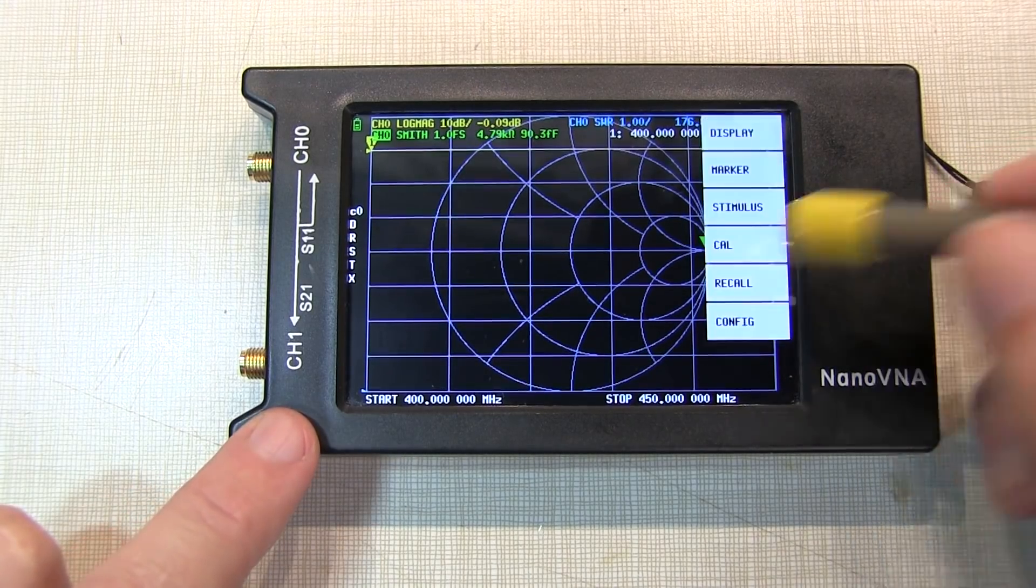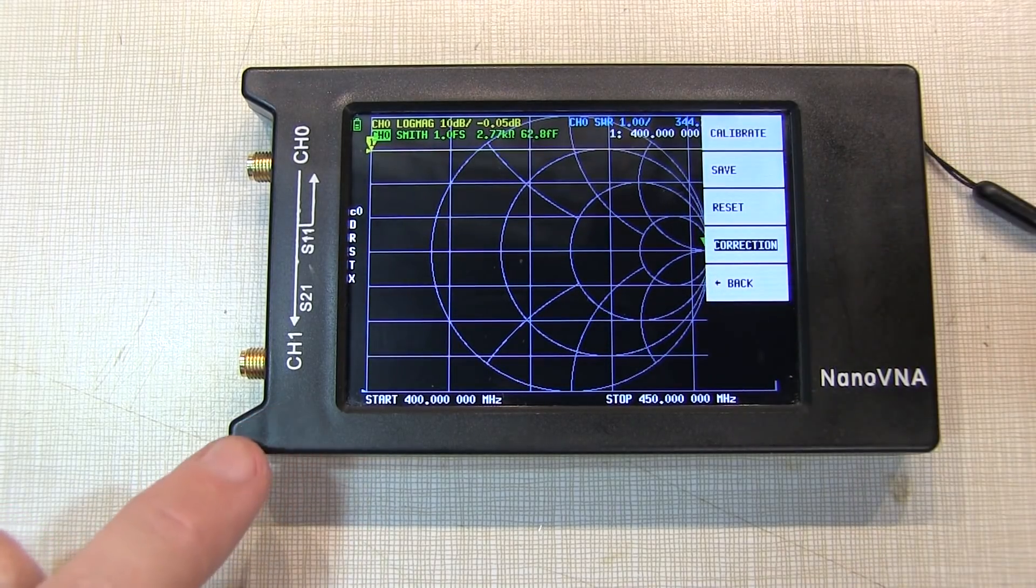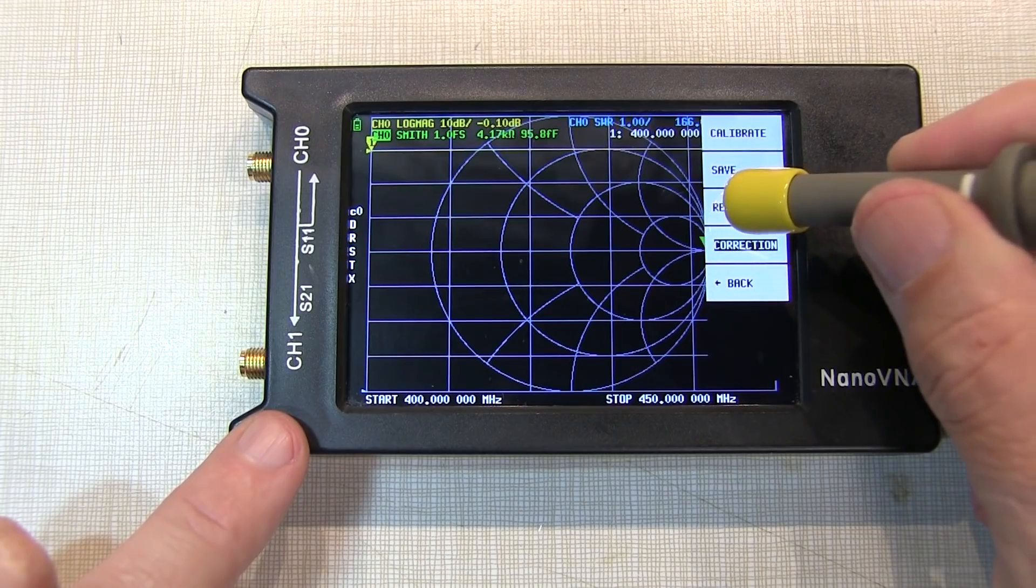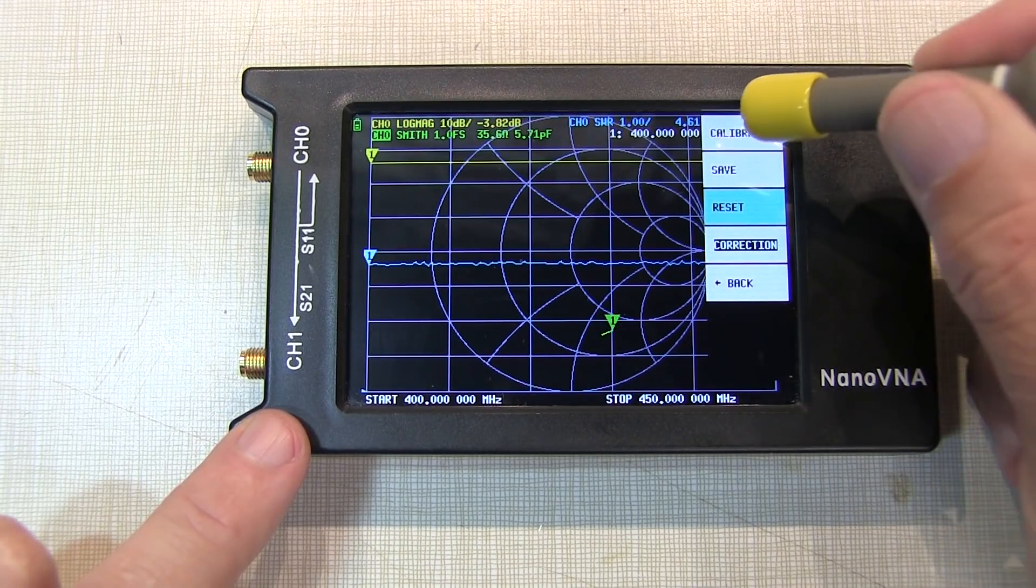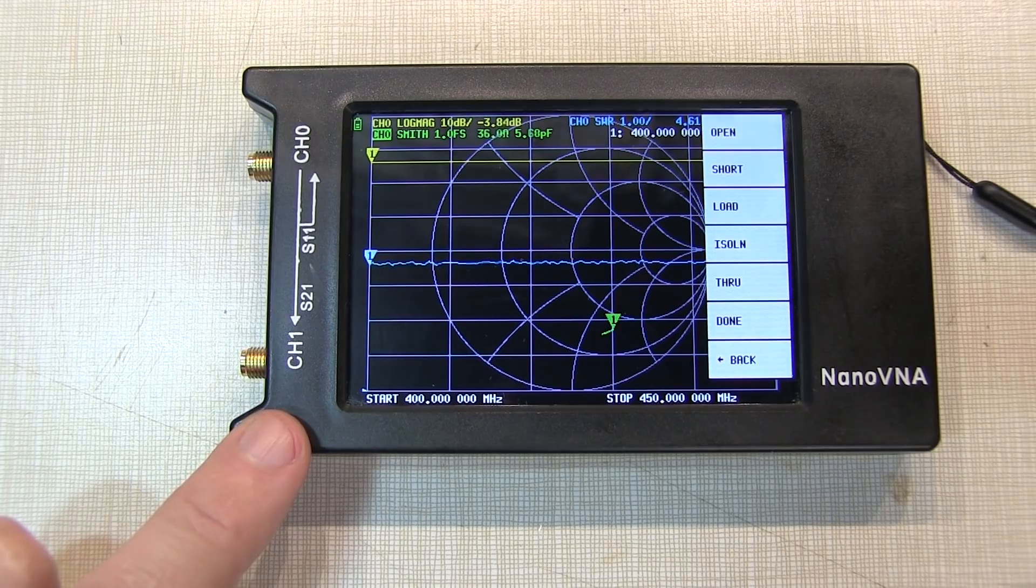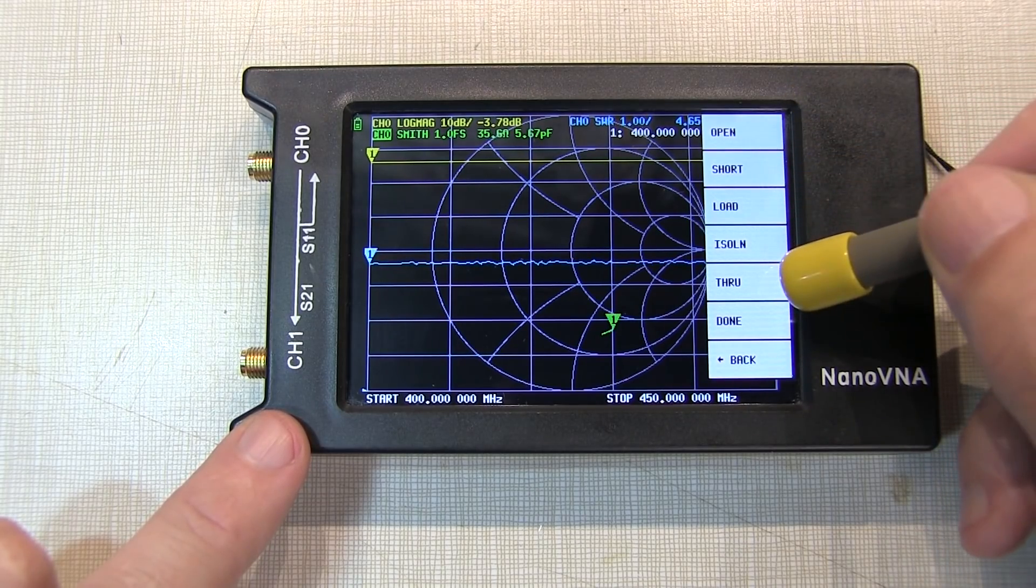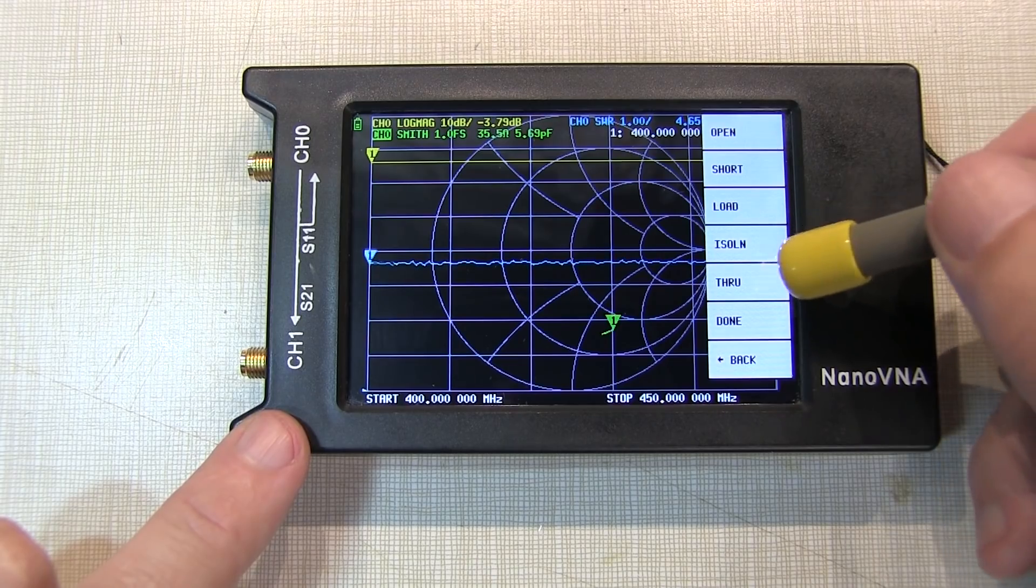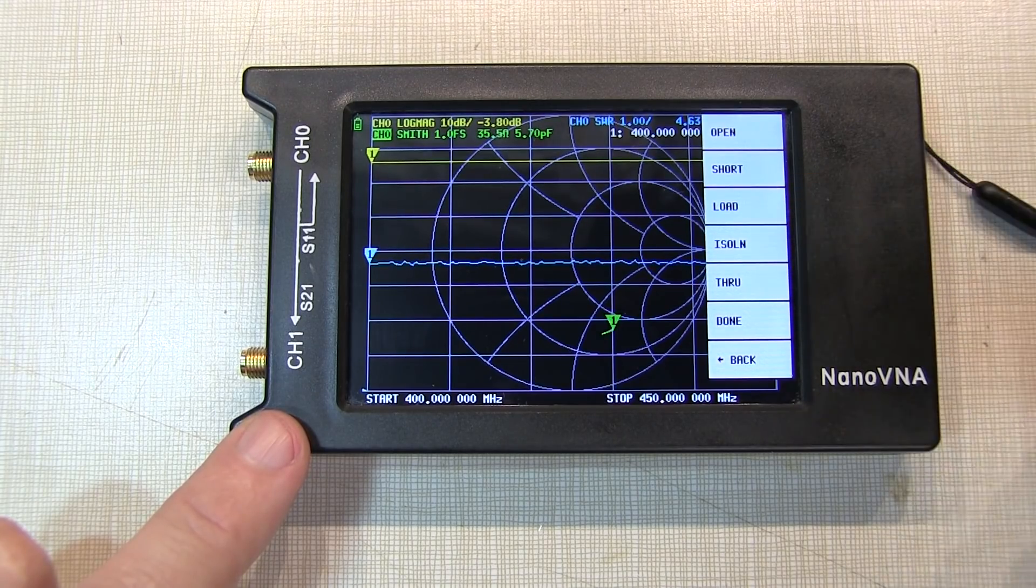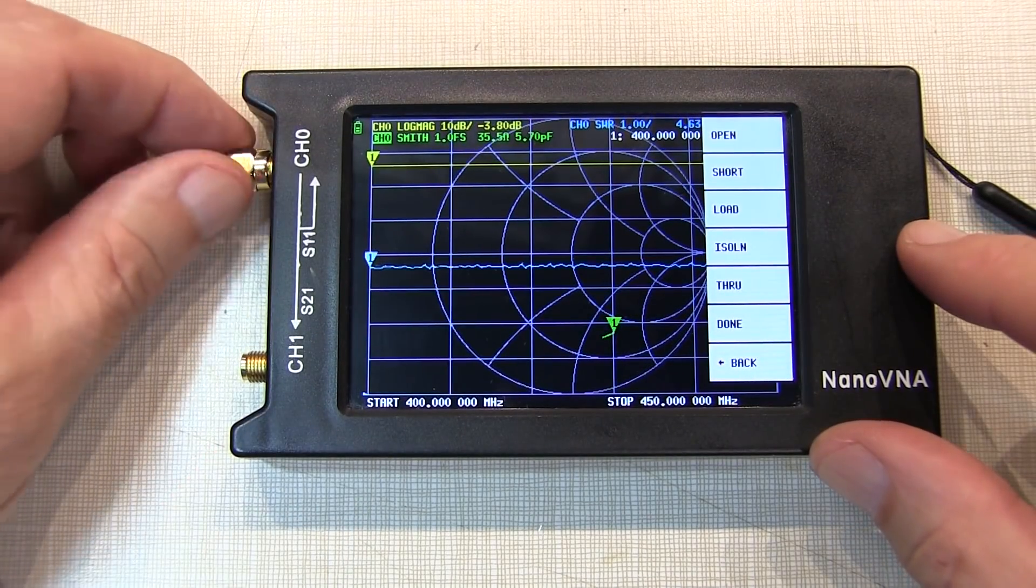So we do that by going into the Cal menu, and we do a reset to clear out the current calibration, and then hit calibrate. And we can see we've got our open, short, load, and then isolation, and through. We're only doing SWR measurements, so we're not going to do these latter two. We're only going to do our open, short, and load.